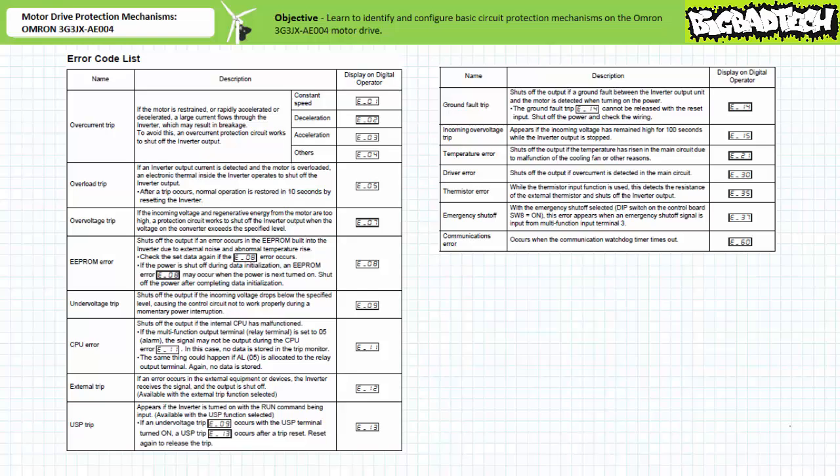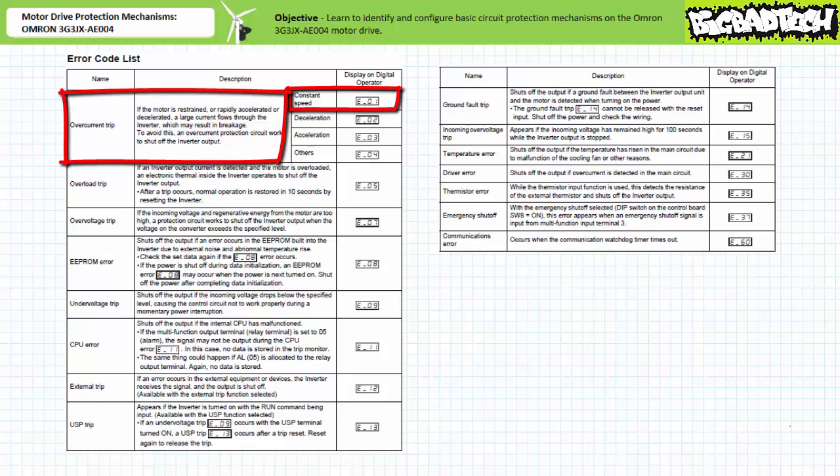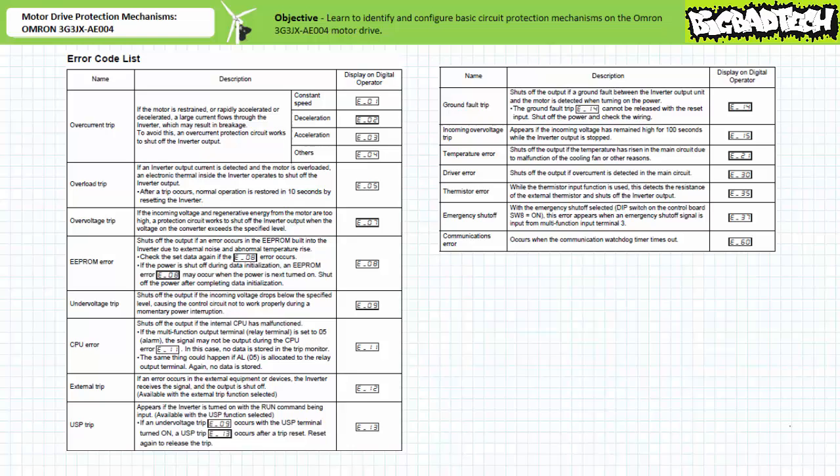For example, error code E01 indicates an overcurrent trip while in constant speed mode. The user's manual further specifies that an overcurrent trip while in constant speed mode will depower the output. The default response for most of these important fault conditions is to depower the output and signal an alarm with the appropriate error code. However, the OMRON 3G3JX AE004 motor drive also allows the user to customize this response depending upon the needs of the system.